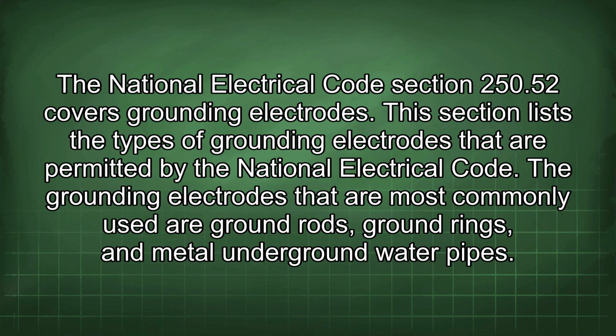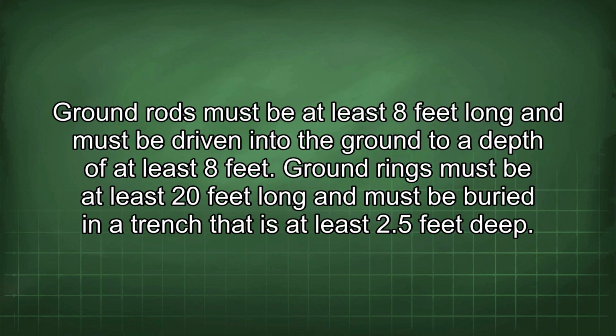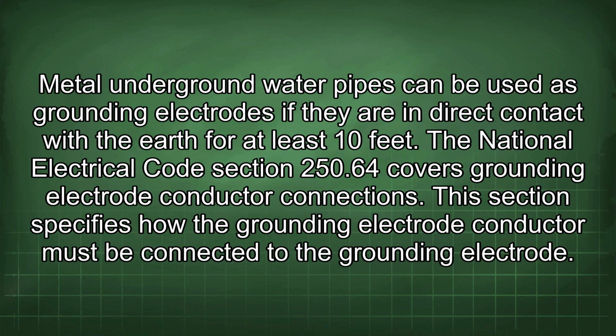The National Electrical Code Section 250.52 covers grounding electrodes. This section lists the types of grounding electrodes that are permitted by the National Electrical Code. The grounding electrodes that are most commonly used are ground rods, ground rings, and metal underground water pipes. Ground rods must be at least 8 feet long and must be driven into the ground to a depth of at least 8 feet. Ground rings must be at least 20 feet long and must be buried in a trench that is at least 2.5 feet deep. Metal underground water pipes can be used as grounding electrodes if they are in direct contact with the earth for at least 10 feet. The National Electrical Code Section 250.64 covers grounding electrode conductor connections. This section specifies how the grounding electrode conductor must be connected to the grounding electrode.